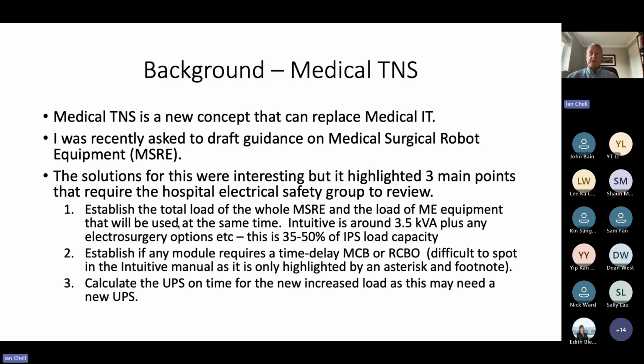Secondly, what a lot of hospitals have been missing is that you have to establish if one module requires a time delay miniature circuit breaker or RCBO. And it's difficult to spot this because I know in the Intuitive manual, which is for the Da Vinci device, it's only highlighted by an asterisk and then a footnote, and everybody has been missing it. This brings problems for supplying the new robot surgical arm, okay?